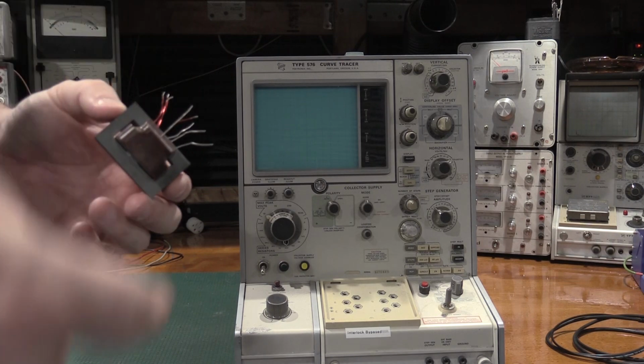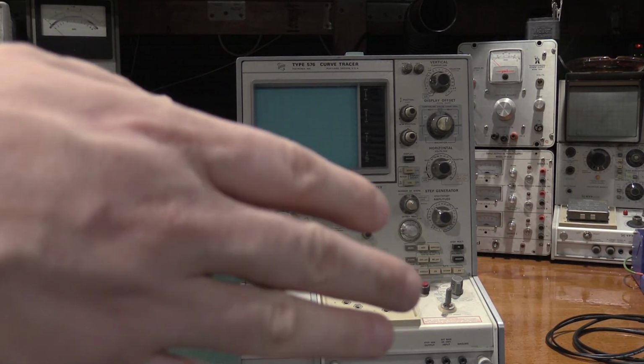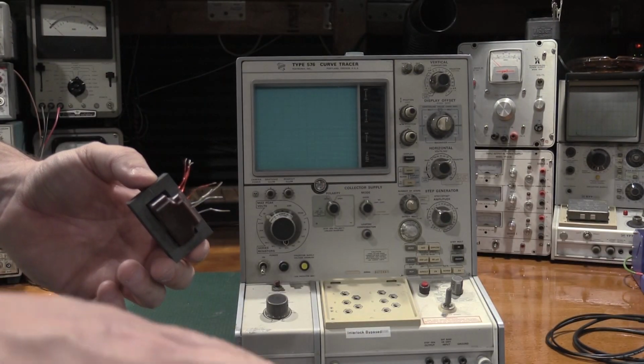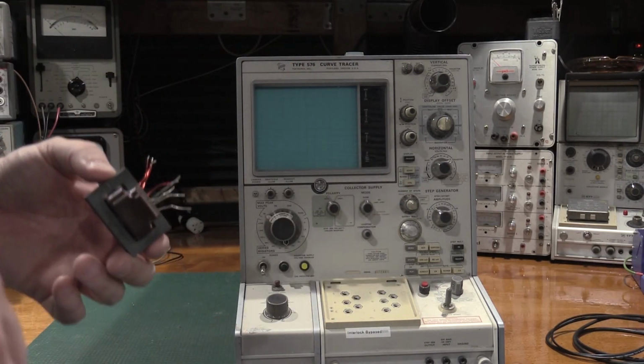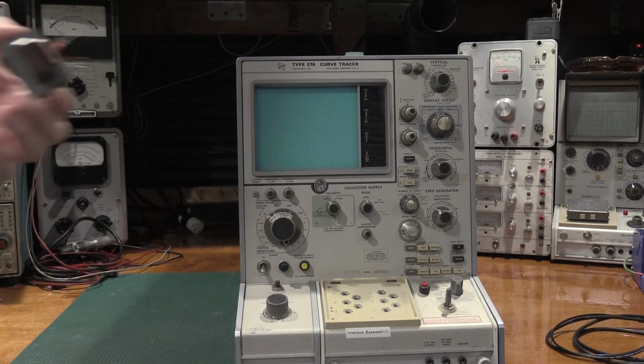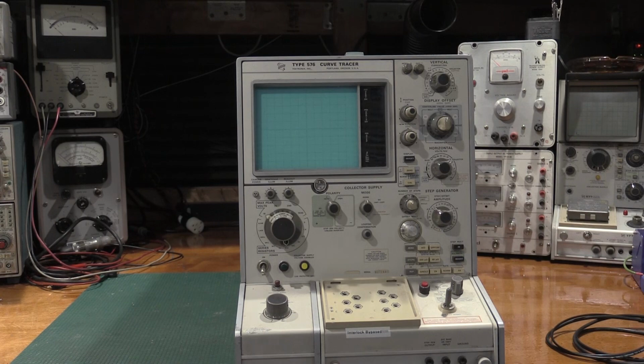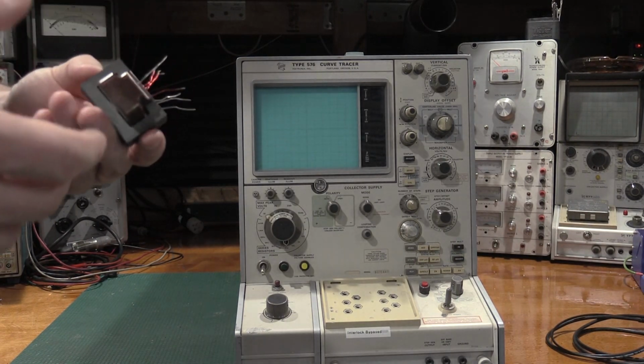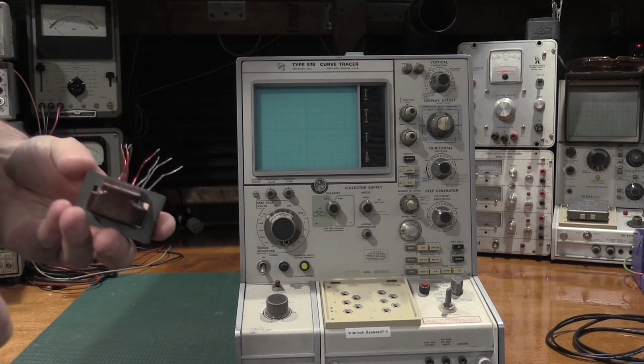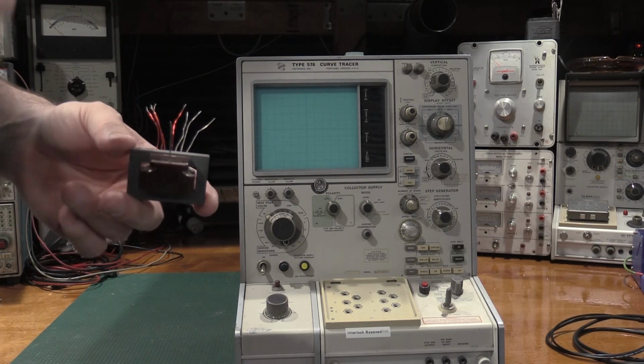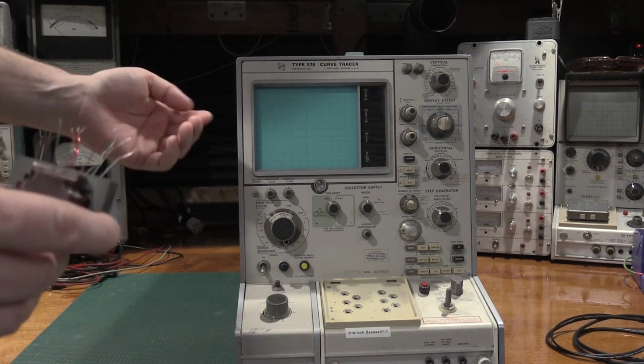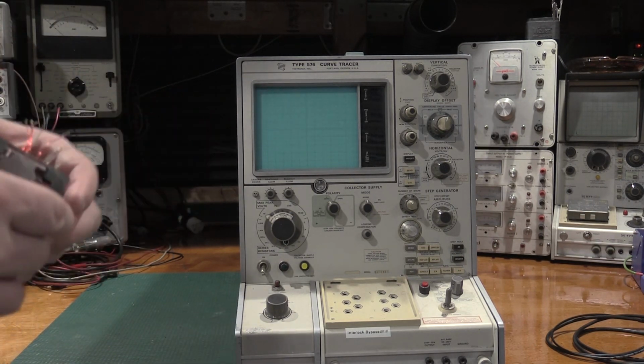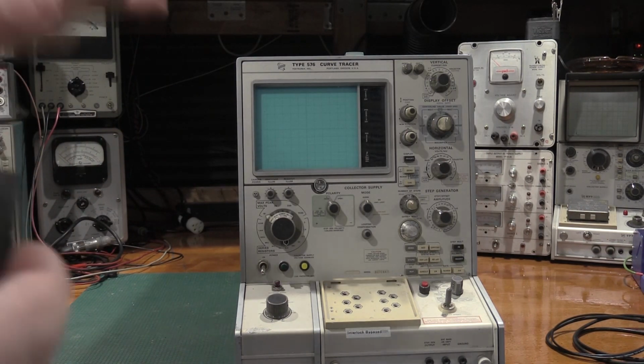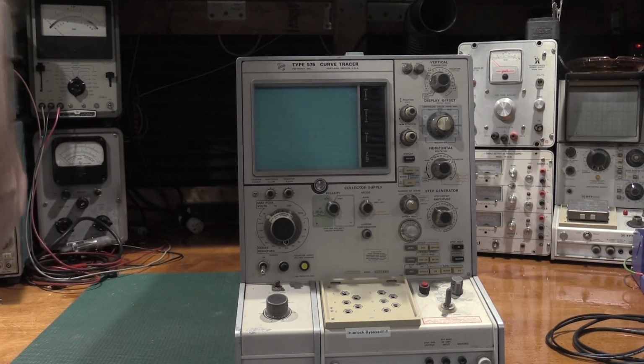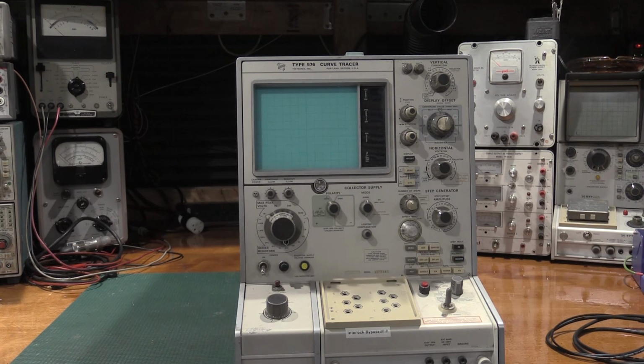So I'd hear this clicking on the bench. It was like on, off, on, off, and obviously not healthy for the unit. But that was the symptoms that my high voltage transformer exhibited. The parts unit I had the silicone transformer, so I ended up putting the Tek transformer in here. I do have 2 spare transformers.